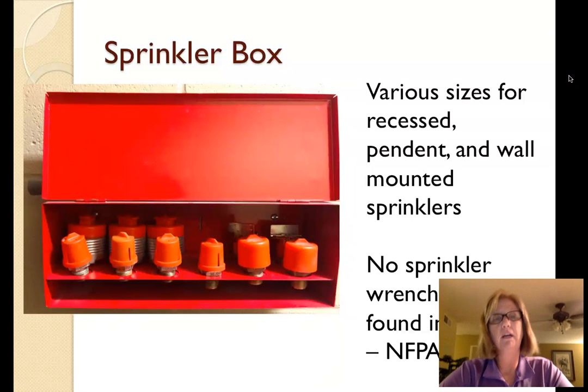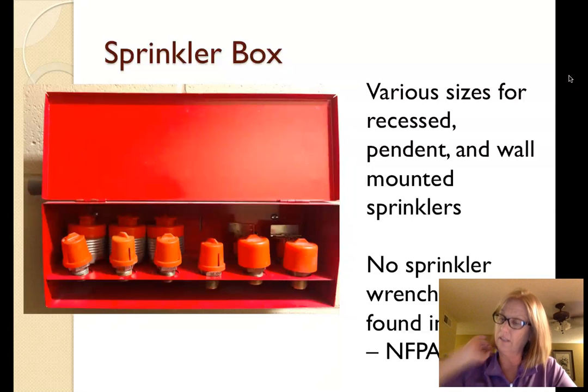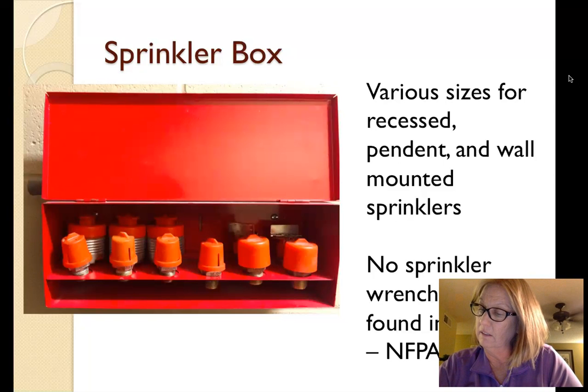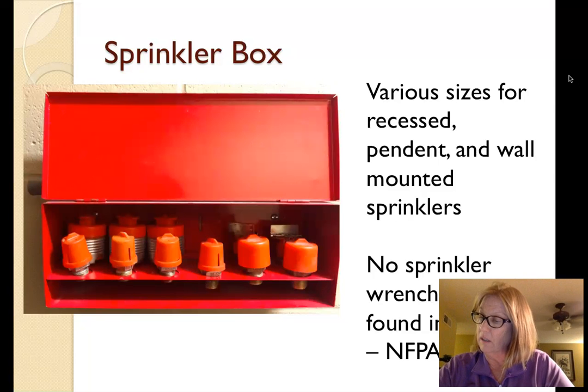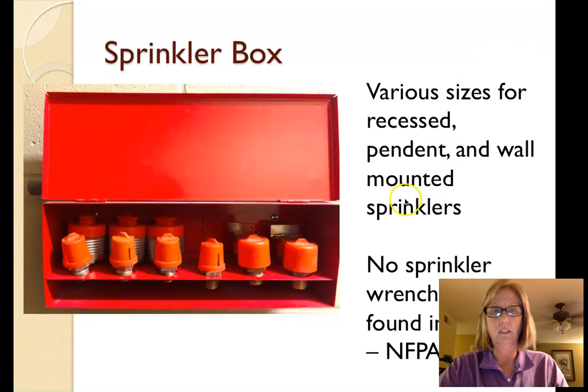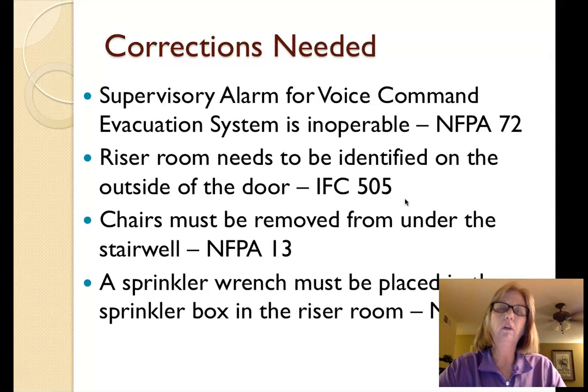There we go. The sprinkler head box inside the riser room contained a variety of sprinkler heads as required by NFPA 13 that were specific to this building's needs. But one thing that was missing per NFPA 13 was that there was no wrench inside of there. So that was considered a violation. So there were only a few corrections that needed to be made.